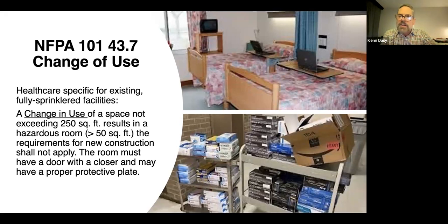Sanitizer, by the way, cannot have more than 10 gallons of sanitizer in a compartment. So I have seen a number of sites where you may have several dozen cases of sanitizer, which way exceeds 10 gallons, and surveyors have been citing that. But you are permitted to have an automatic closer added to the door of this patient room and turn it into storage. And that's all you have to do.